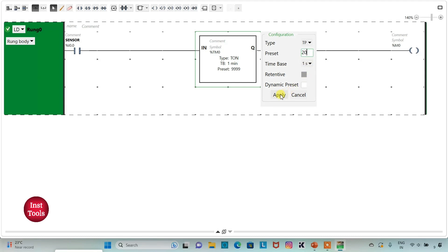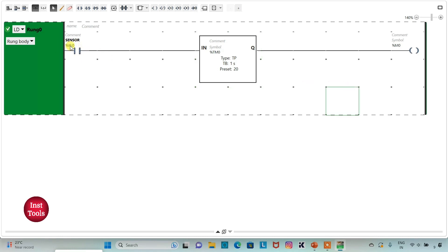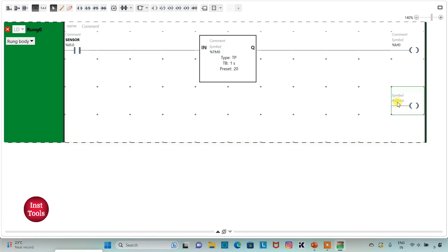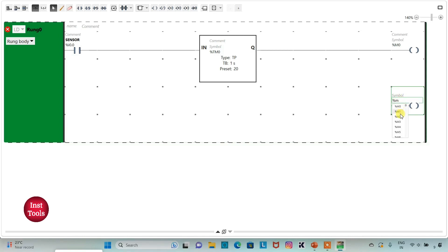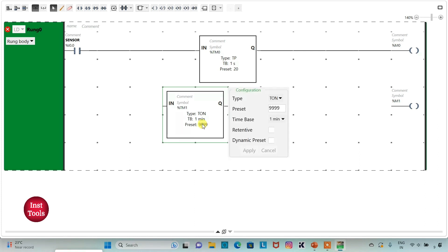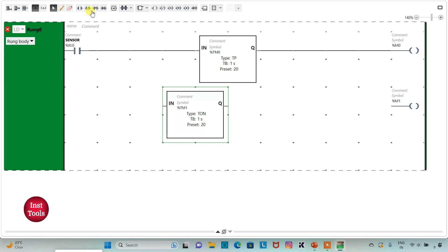I will change the time base and keep the preset value as 20, then click Apply. So when the sensor detects any movement, M0 will get true for 20 seconds. With M0 I will insert one more coil and assign address as M1. For M1 I will use a TON (on-delay timer) and change the time base to 1 second with preset value as 20, then Apply.